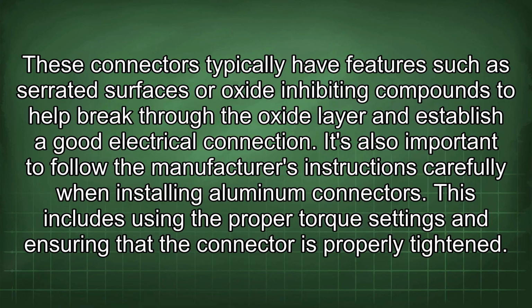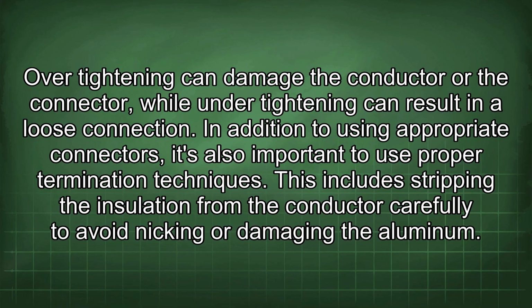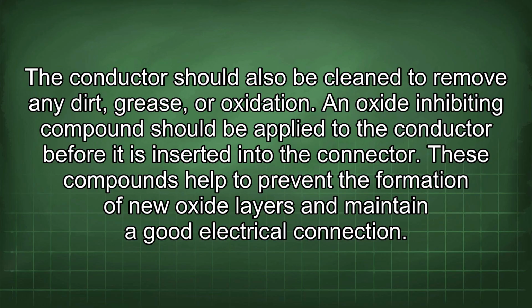It's also important to follow the manufacturer's instructions carefully when installing aluminum connectors. This includes using the proper torque settings and ensuring that the connector is properly tightened. Over-tightening can damage the conductor or the connector, while under-tightening can result in a loose connection. In addition to using appropriate connectors, it's also important to use proper termination techniques. This includes stripping the insulation from the conductor carefully to avoid nicking or damaging the aluminum. The conductor should also be cleaned to remove any dirt, grease, or oxidation. An oxide-inhibiting compound should be applied to the conductor before it is inserted into the connector. These compounds help to prevent the formation of new oxide layers and maintain a good electrical connection.